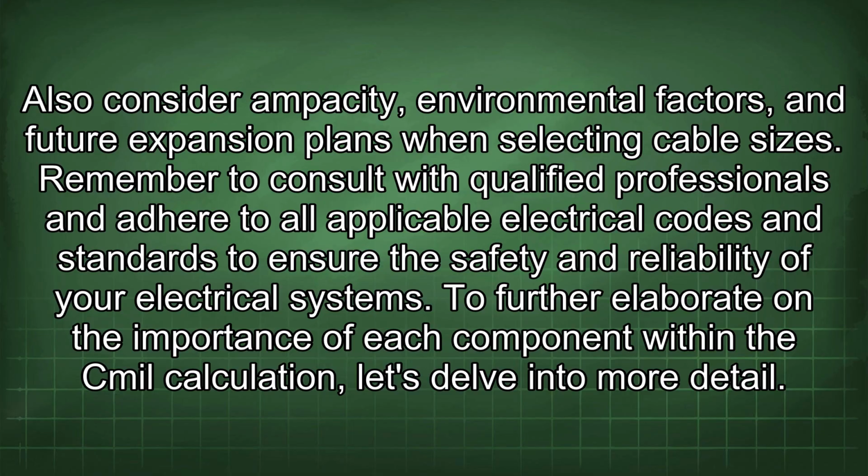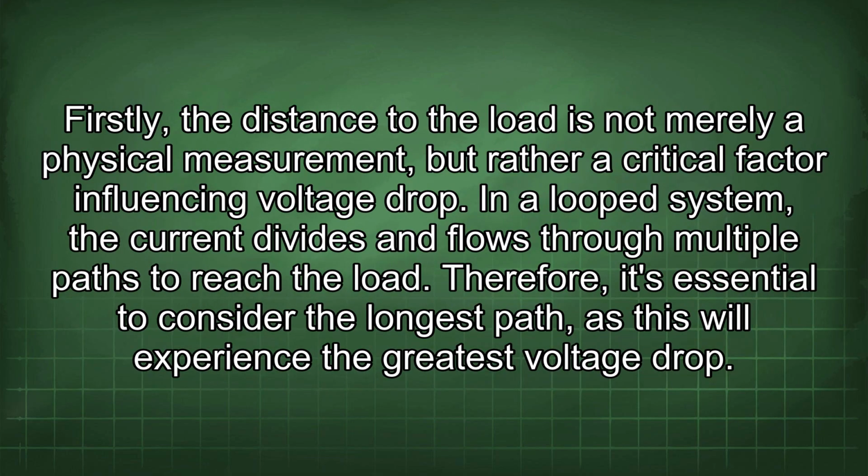To further elaborate on the importance of each component within the Cmil calculation, let's delve into more detail. Firstly, the distance to the load is not merely a physical measurement, but rather a critical factor influencing voltage drop. In a loop system, the current divides and flows through multiple paths to reach the load. Therefore, it's essential to consider the longest path, as this will experience the greatest voltage drop.